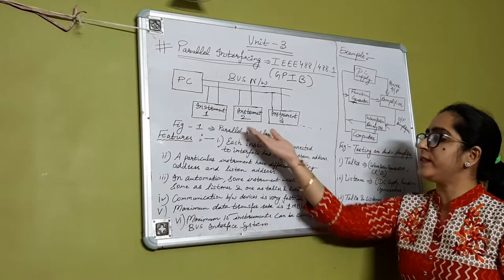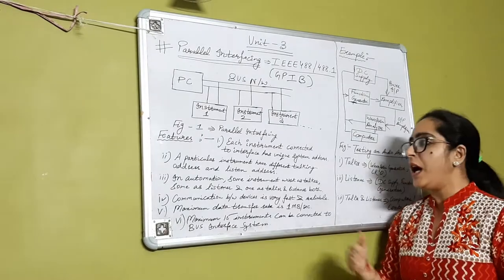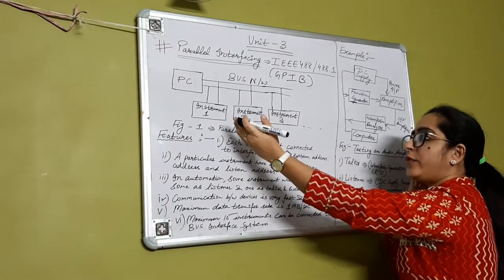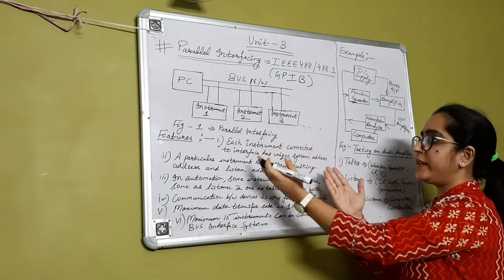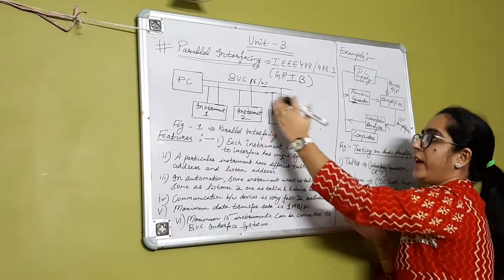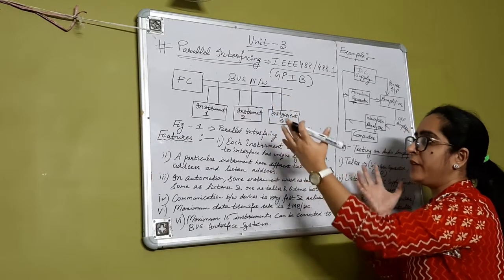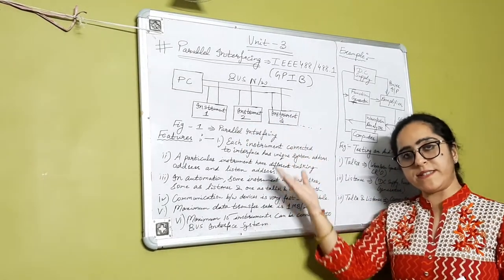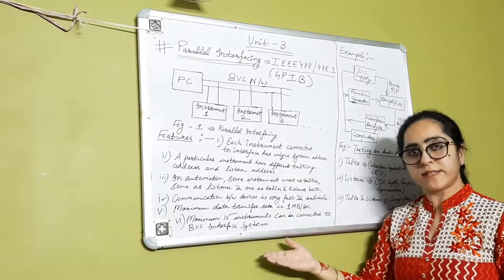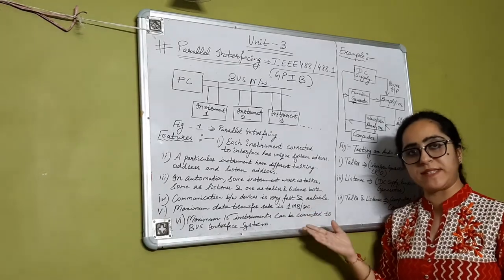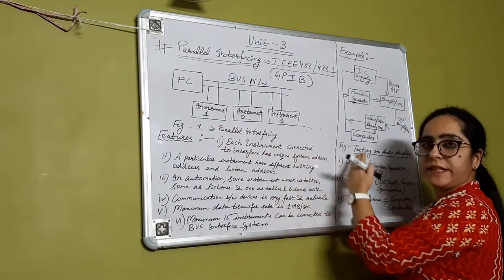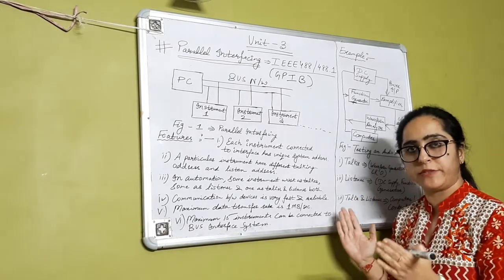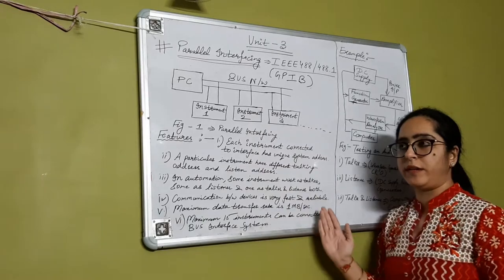The advantage of using the IEEE 488 network is that it makes the process very convenient, as a lot of hardware interfacing is reduced. It brings up to a single interface network through which more hardware and wiring can be reduced. It is easy to reconfigure, very fast, and the maximum data transfer rate is 1 megabyte per second. A maximum of 15 instruments can be connected for a particular application.